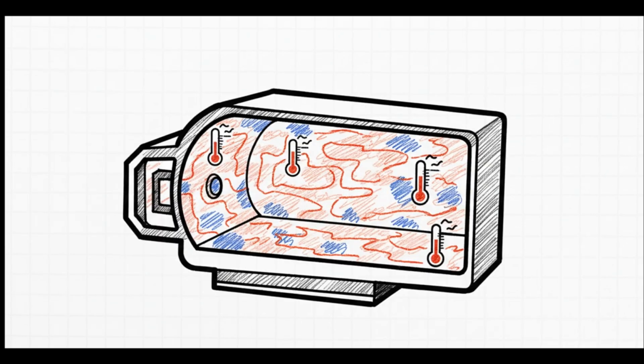So the very first drill is to map the temperature of the empty chamber. Here's a little counterintuitive fact: heating an empty chamber evenly is actually harder than heating a full one. Without a bunch of stuff in there to absorb and spread the heat around, you get more hot and cold spots. So this is a surprisingly tough first test.